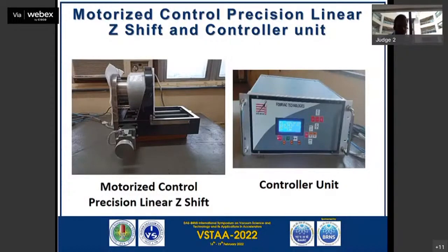Then I'll ask one question. Yes, sir. This embedded controller you are using, what sort of isolation is there between the high voltage side, I mean, it may be 230 volts only, and the control side? Yes, sir. For digital signals, we are using relays, which give physical isolation, whereas for analog signals, we are using analog isolators, which give insulation of up to 3 kV. Okay.